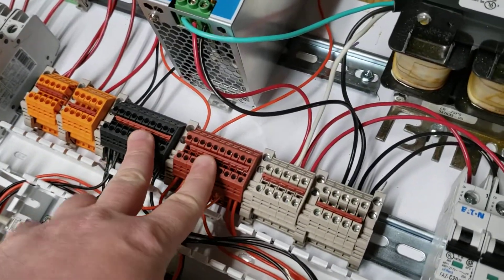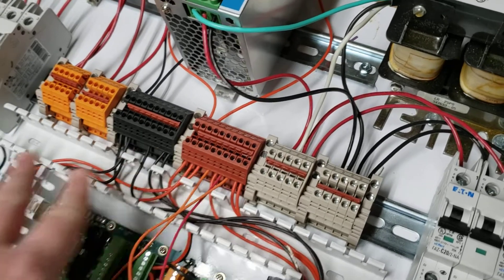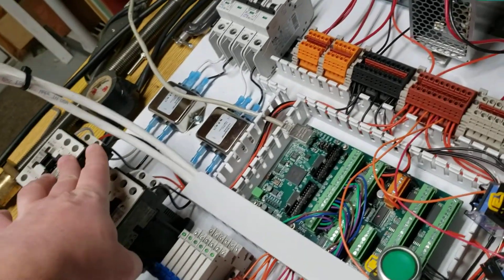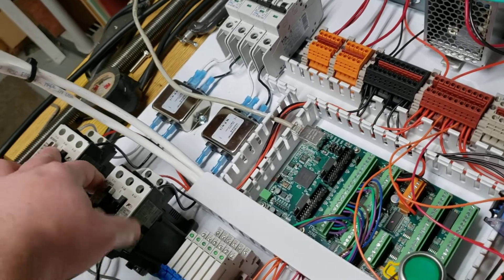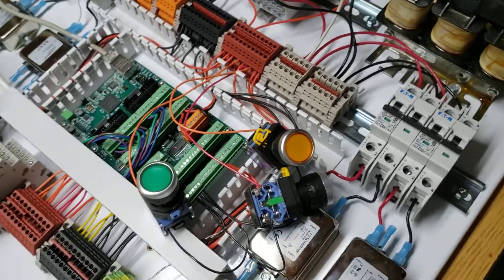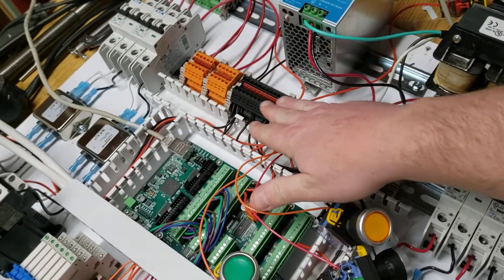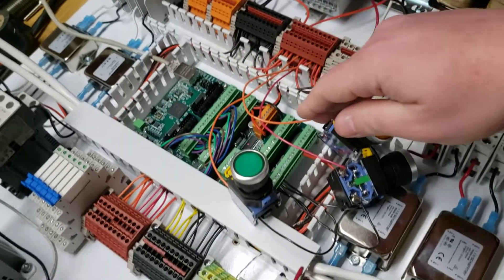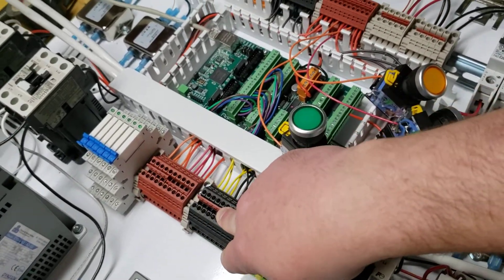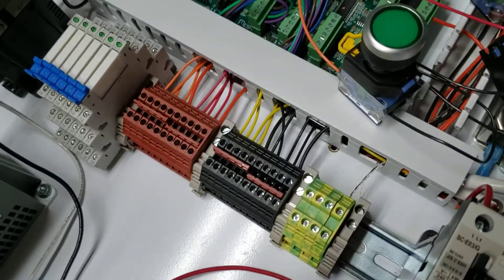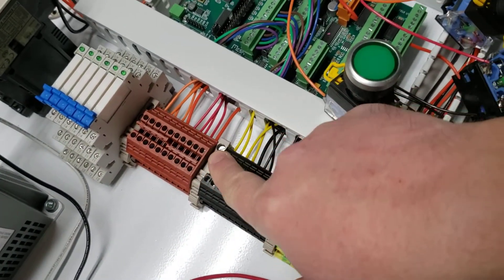The 24 volt distribution goes to each of the contactors. That's what triggers them to engage. When it sees 24 volt, they engage. From the 24 volt blocks here, I distribute it down to these 24 volt blocks here. And what these are, are my send and return for my alarm signals to each of the drives.